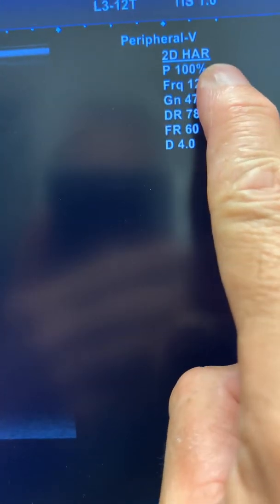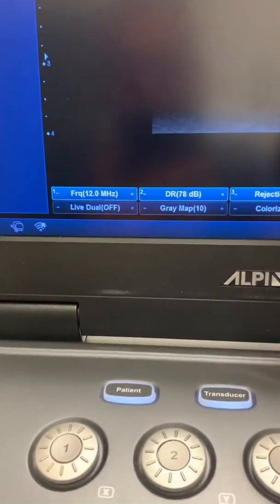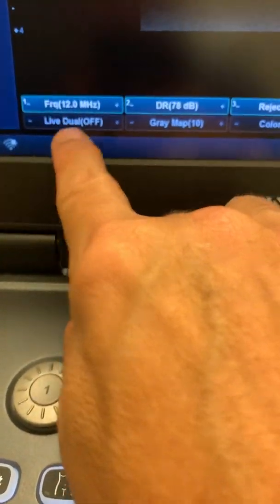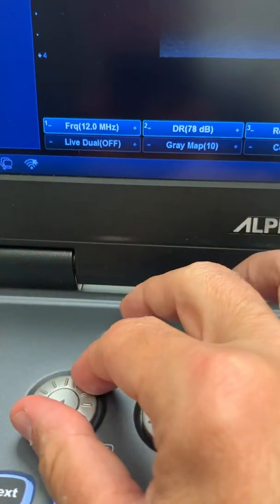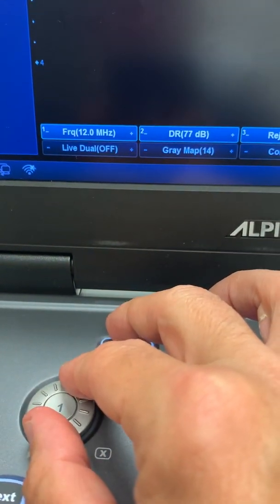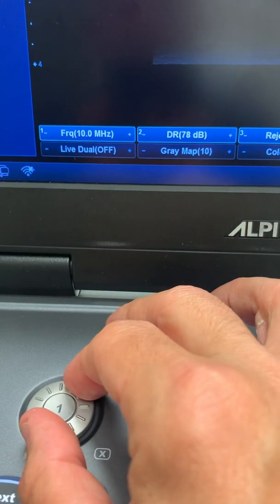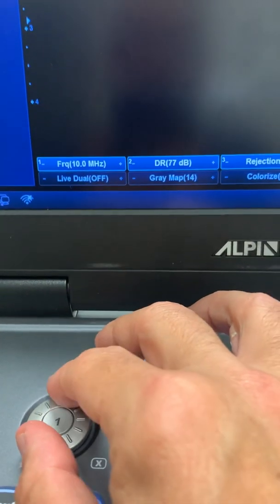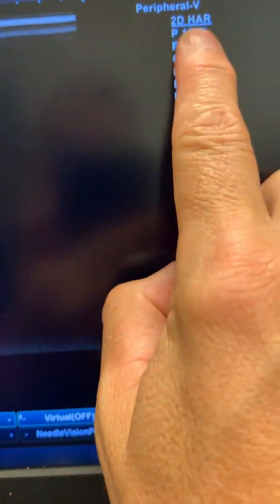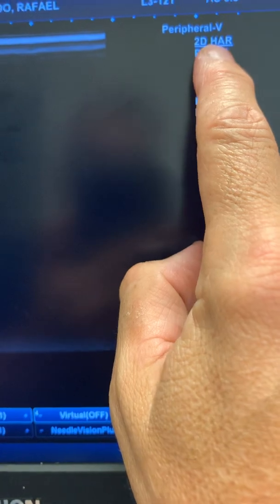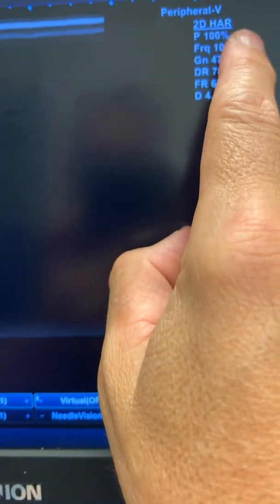When you click there, you see H A R - that means the machine is doing harmonic imaging now. In this menu here, controlled by knob number one, you can actually change the frequency for the harmonic imaging. So that would be 10, and this is H A R which is the second harmonic, tissue harmonic imaging.